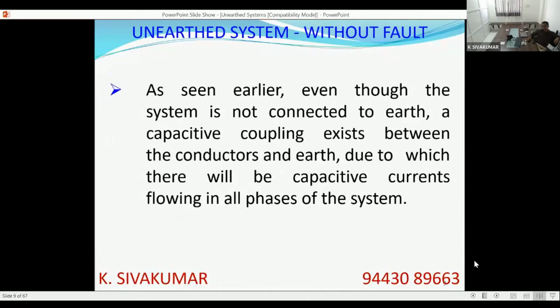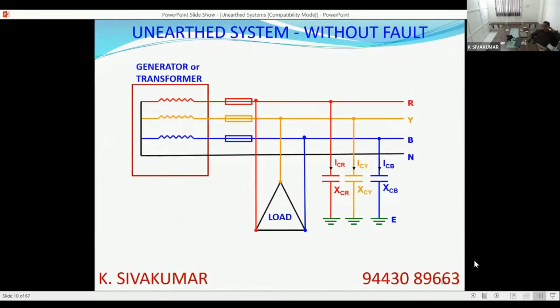Now, even though the system is not connected to earth, a capacitive coupling exists between the conductor and earth, due to which, whenever there is a capacitance, there will be capacitive currents flowing in the system. So you can see, when we have XCR, XCY and XCB, you will also have ICR, ICY and ICB. These capacitive currents will start flowing in the system through the earthed coupling capacitor.